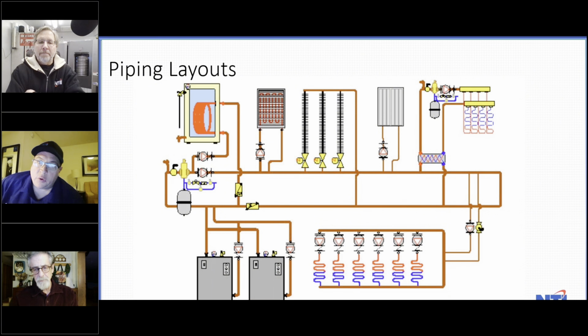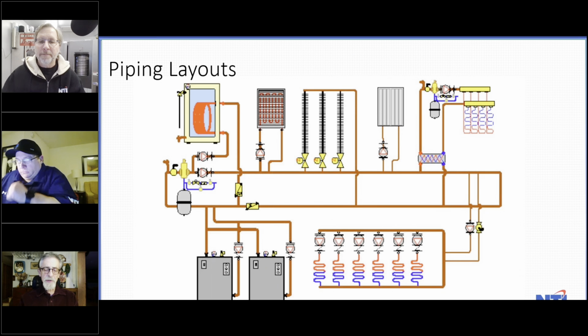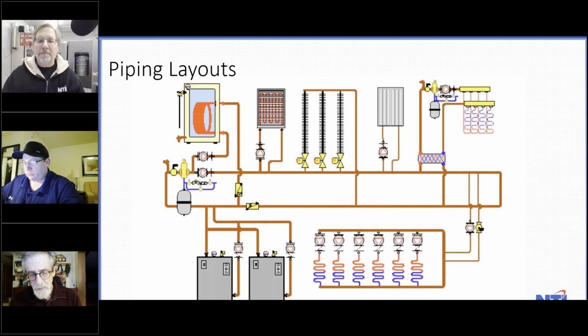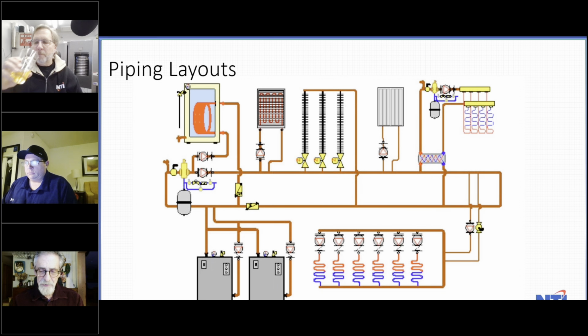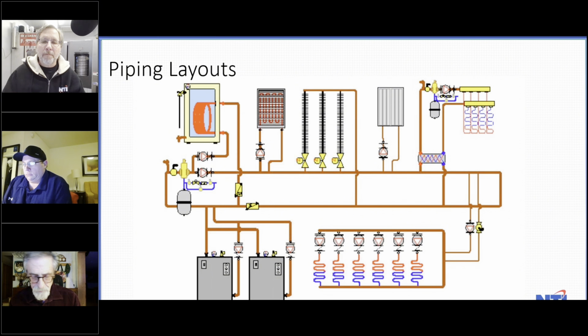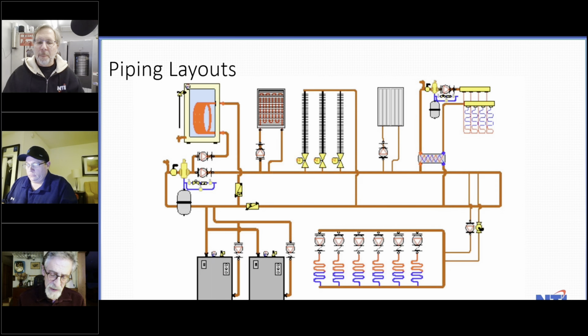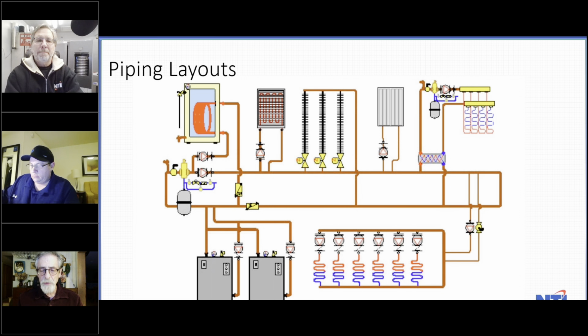That's a good point, because if you pre-mix it, you're not going to introduce air, and glycol will entrain air in the system, especially in a water tube boiler. The glycol will entrain air. Glycol is a necessary evil in this case, but glycol in a hydronic heating system introduces its own set of problems. It decreases the heat transfer efficiency. It increases the viscosity, which makes it harder to pump. And like I said, if you don't pre-mix it, it's not going to mix on its own. So be careful with glycol.